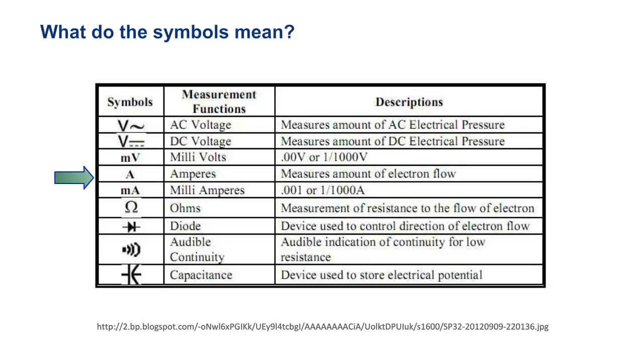A large A, that's amps. Amps is the push that makes the motor turn. So the bigger the motor, the more horsepower, the more amps. Here's the good news. If you don't like dealing with voltage, then measure amps. Because amps are measured by a clamp-on type amp meter. Taking into consideration, it's not just measuring amps, but amps is also affected by voltage. So if you know your amps are not quite right, then you might need to pursue checking the voltage. Amps can also indicate a bad motor, bad winding I should say. It's a solid number. You'll see an in-rush current where the amps will spike, sometimes one and a half to two times what the normal one is, and then they steady out. It'll give you a good picture of what's happening in the motor.